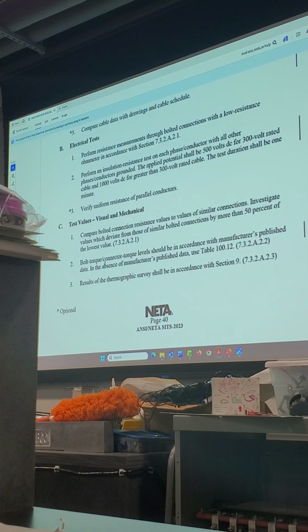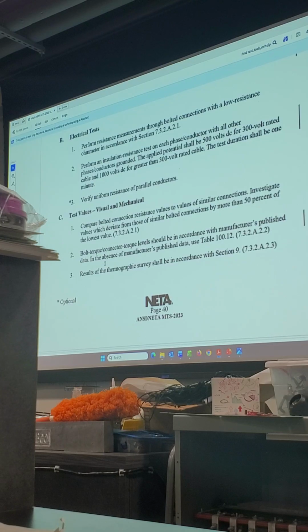In this case, they're small wires, so you won't always torque your low voltage screw connections, but you might. Number 3 is going to be a thermographic survey. Keep in mind, these three come together - your ductor, your torque wrench, and your thermographic survey. Those are the big 3 of electrical connections.